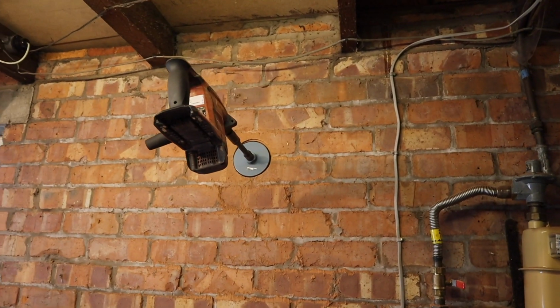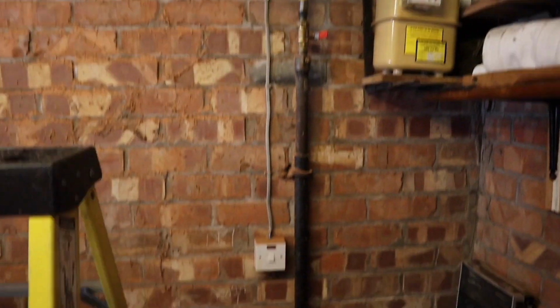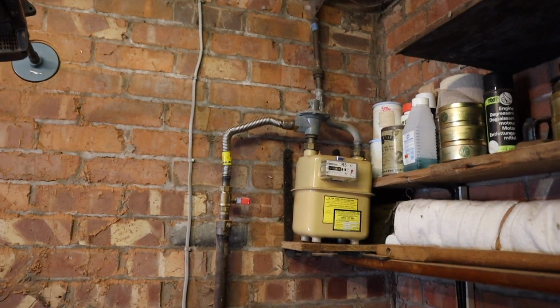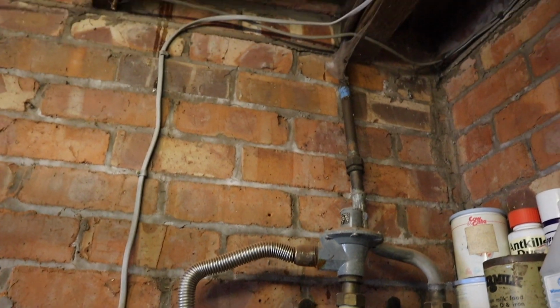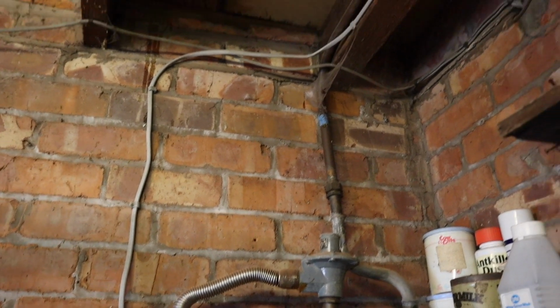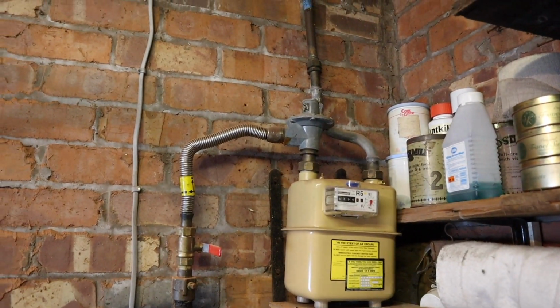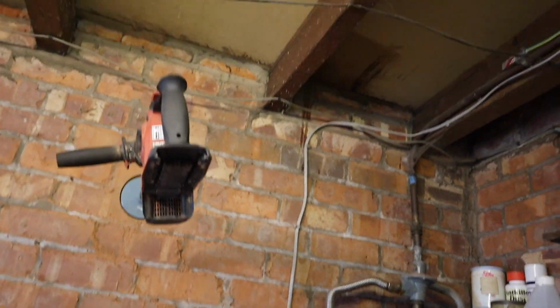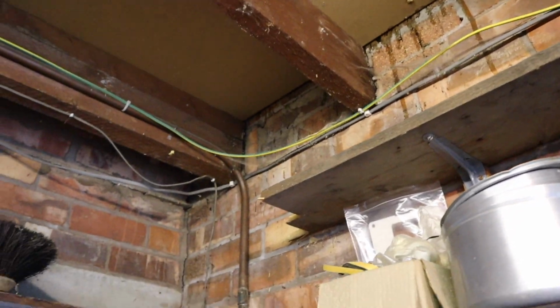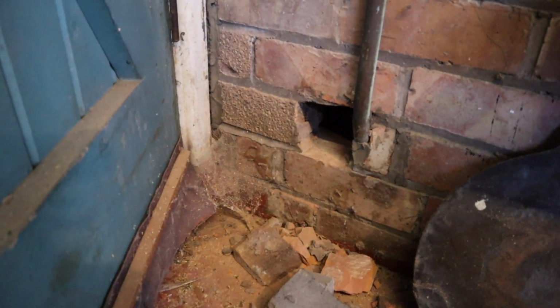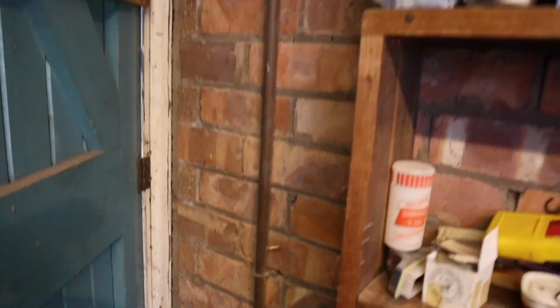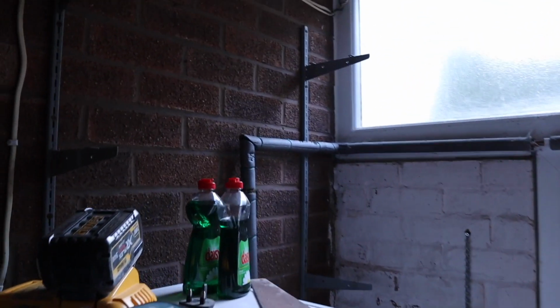So this is where the boiler's going in the garage. So there is a few spare for us and there's not much of a gas run, but we will have to change that lead off there, and that is imperial pipe, so we will need to leave that pipe because that's staying for the kitchen. We're running the gas down then to the boiler. Then we're bringing the flow return across the garage, and then we're coming down behind this door and we're going under the floor there, so we'll have to sleeve the pipes going through there. The hot and cold water is here, so we're going to have to go through into the toilet here. That's the cold pipe there, that was the hot, and we're going to have to go up through there. So that's where we're going to pick up the supplies from.